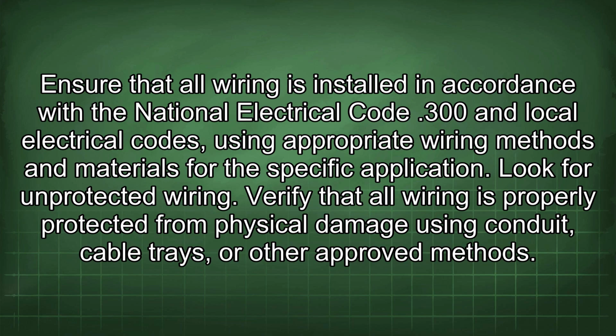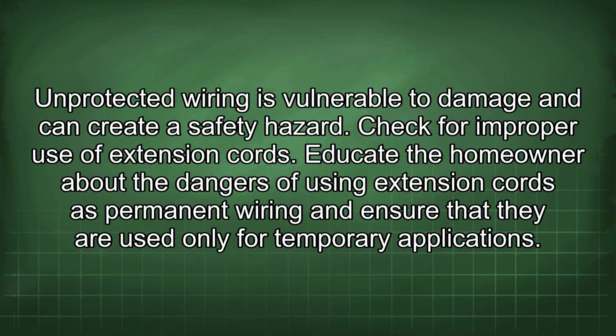Check for proper wiring methods. Ensure that all wiring is installed in accordance with the National Electrical Code 300 and local electrical codes, using appropriate wiring methods and materials for the specific application. Look for unprotected wiring. Verify that all wiring is properly protected from physical damage using conduit, cable trays, or other approved methods. Unprotected wiring is vulnerable to damage and can create a safety hazard.